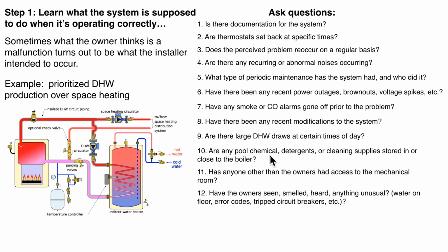Who's had access to the mechanical room other than the owner? Quick true story here. Town hall project, court night. We got a bunch of people standing around in the hall that are a little bit upset because they're there to pay tickets and fines and so forth. And we had a local case here where the mechanical room was left unlocked and one of the disgruntled people went in there and they saw those valves and just started turning the handles on the valves, figuring this'll fix them. And it did. It shut that whole system down for quite a while. So in general, public buildings, you want to have a lock on a mechanical room.